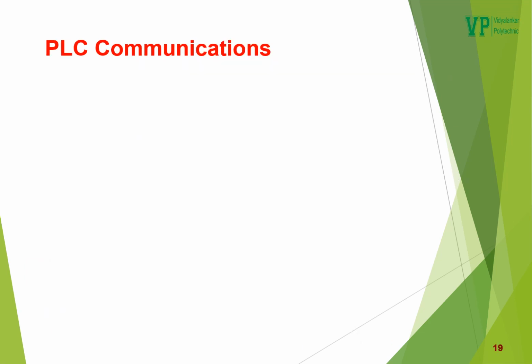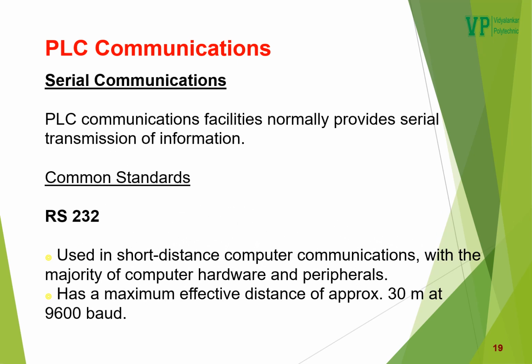PLC communication. Well, it means how do we feed a program to the PLC? PLC can be connected to a programming device, that is, a handheld device or a personal computer through a serial communicating cable. And the recommended standard that we use is RS-232. However, this standard can be effectively used for a smaller distance, which could be as small as 30 meters.